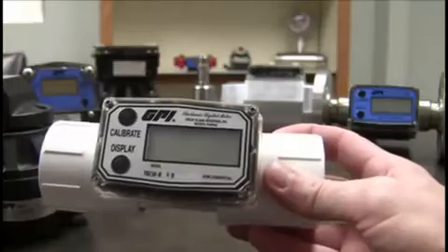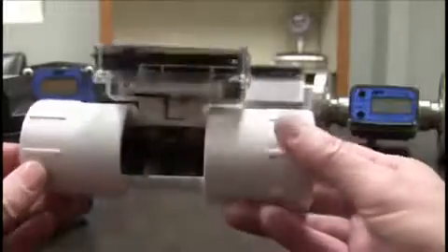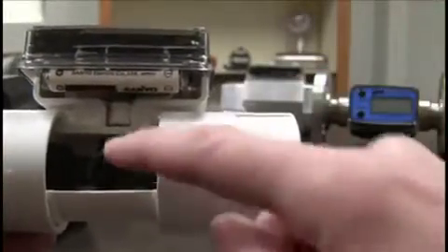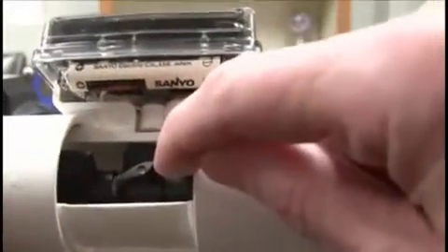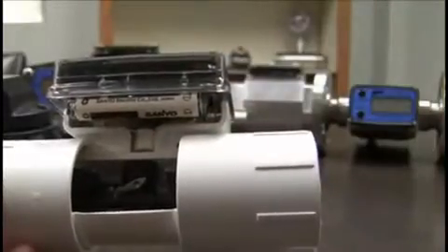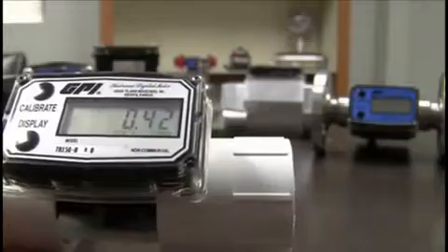And they're pretty simple. Just like most turbine meters, you have your pipe part and then your display part. Now the display creates a magnetic field, which you can see with the magnet right about there. And that magnet creates a magnetic field, so as the turbine spins, which happens when fluid goes through the pipe, it spins that turbine. You can see right about there, it's a little metal hunk in the end of the turbine. So each time that metal hunk breaks the magnetic field, it creates a pulse, and then of course the display counts it. And the display has already been programmed by a calibrator to know exactly how many pulses equals a gallon. And that's really about it with a turbine meter.